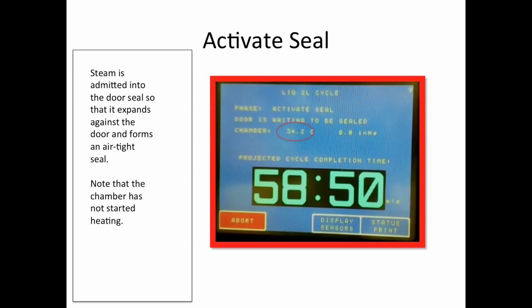Now we're almost ready to begin admitting steam into the sterilization chamber, and that begins with the activate seal phase. Now, steam is admitted into a sort of bladder in the door that causes it to expand tight against the door and form an airtight seal. Now, notice that we haven't started heating up our chamber yet.